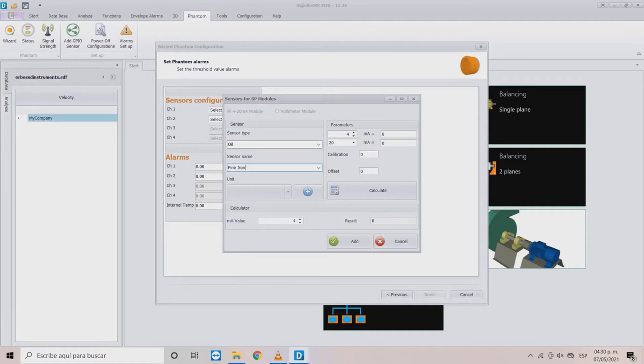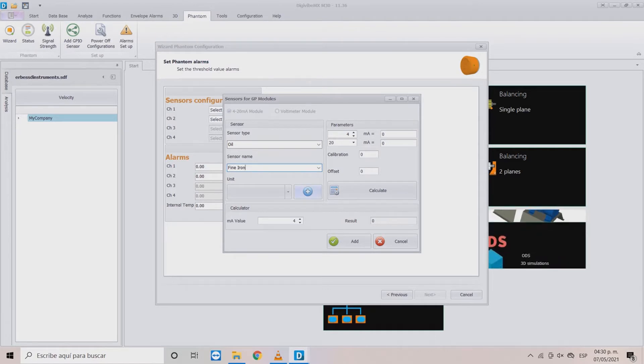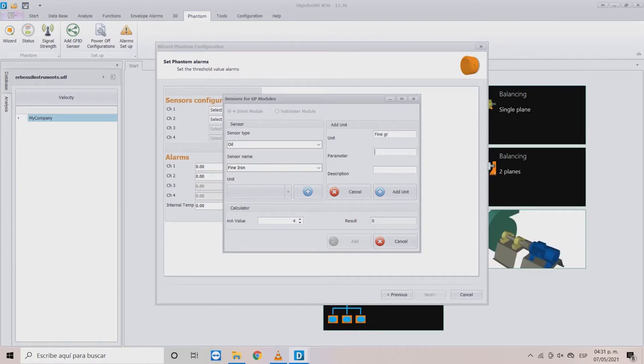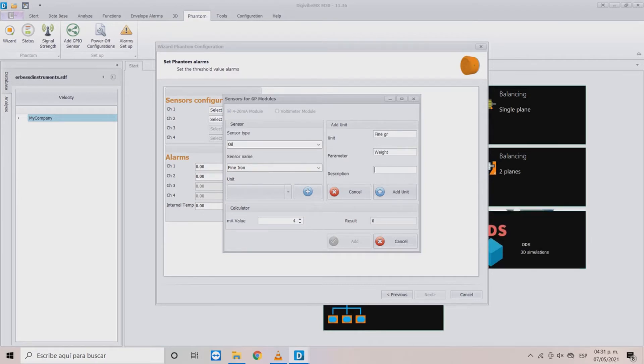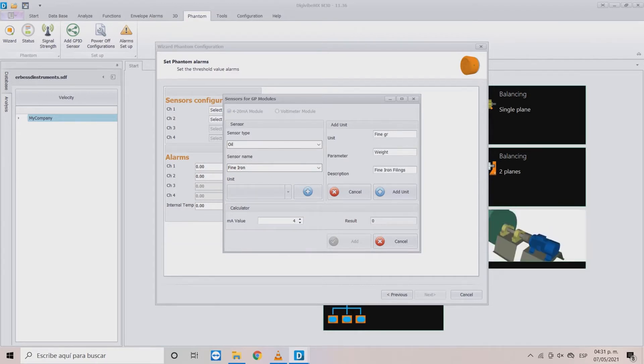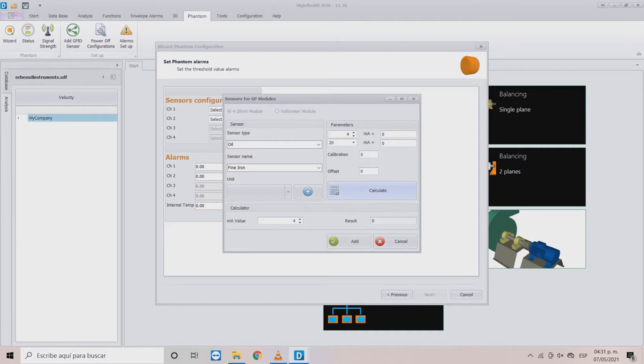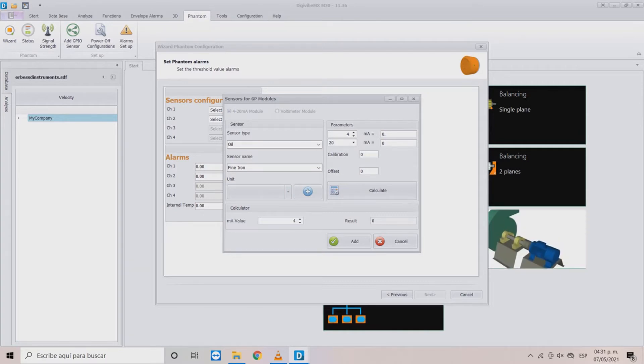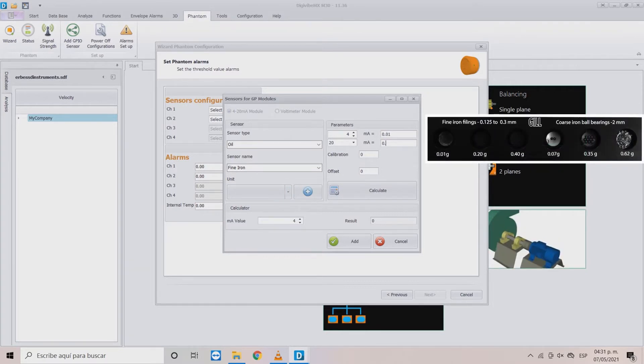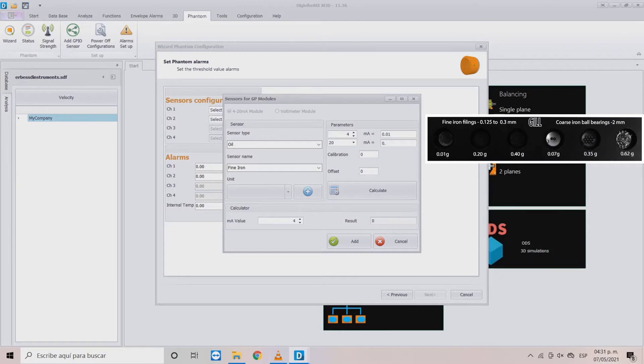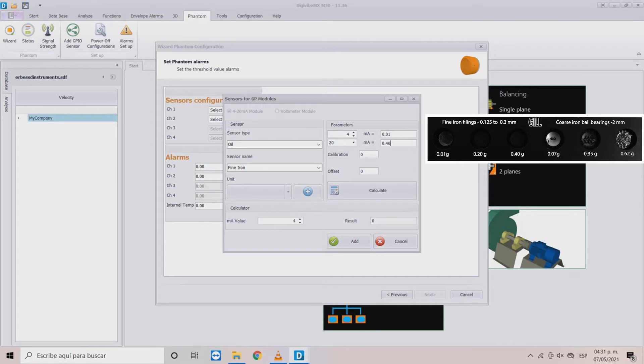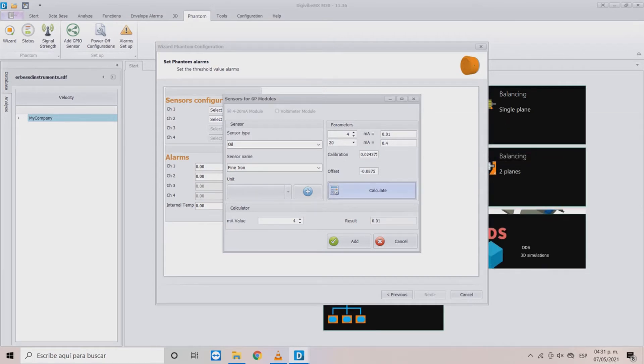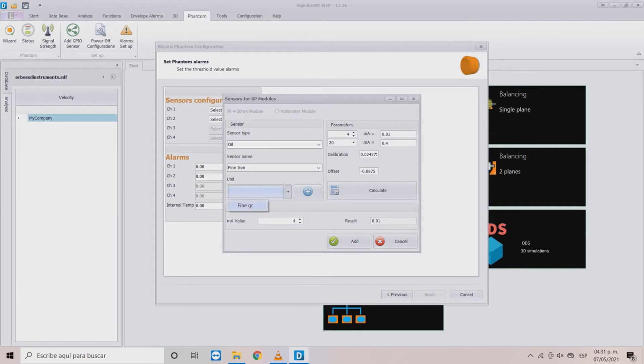We will start with the fine iron unit. This is measured in grams, so we have to define the parameter and description. Once you are ready you can click on add unit. Now you have to set the values for the 4 to 20mA range. We will use the debris strip units to set 0.01 grams at 4mA and 0.40 grams at 20mA. You can click on calculate to see if everything is in order.